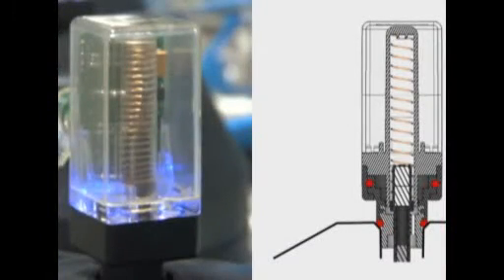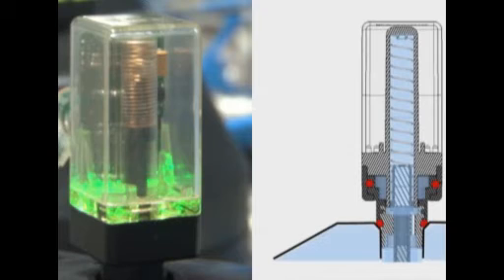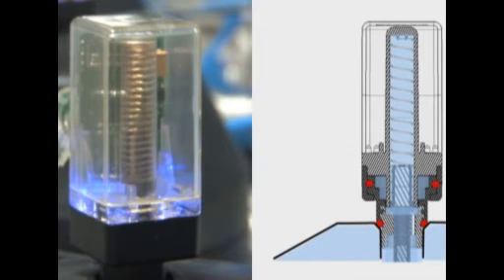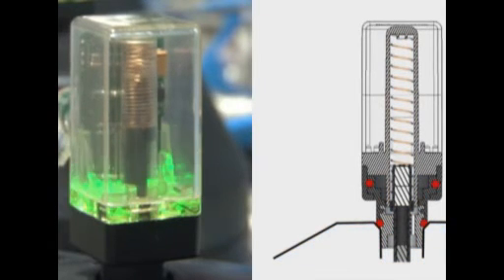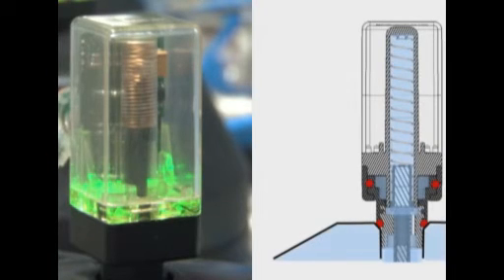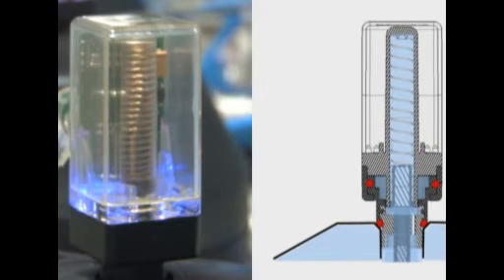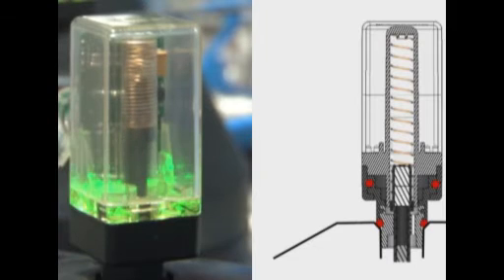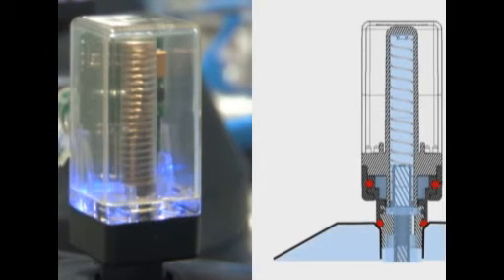The electronic components are hermetically sealed and separated from the mechanical parts. As a result, the areas with the mechanical parts are designed to be pressurized and do not need any dynamic sealing. No longer will you have the sealing problems for fail-safe open or double-acting actuators as in the past. This is the advantage of the limit switch working contact-free.